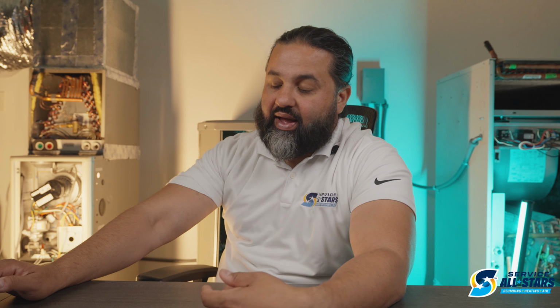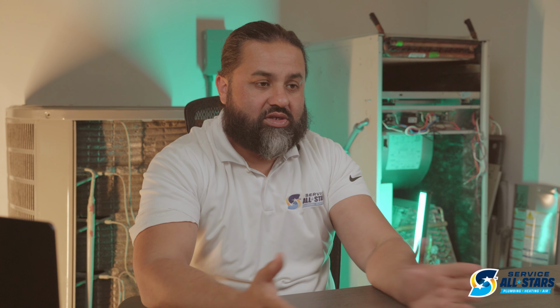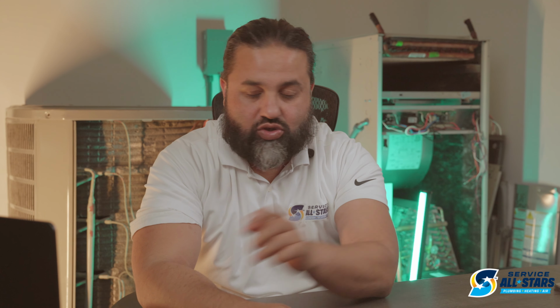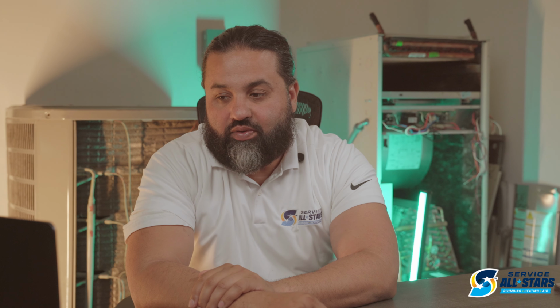So, like I said, our technicians, as they come out to your home, they're going to inform you if you have high static pressure, and we're going to get a second set of eyes out there to confirm the findings of the first technician to make sure that the static pressure is dialed in to where it needs to be, because it's a very urgent and serious issue. If we just leave it like that and not let our clients know, hey, this is what's going on with your system, we're actually doing a disservice to them, and anybody that does that. So I always tell clients, hey, look, if they're like, I'm going to get another estimate, okay, great, go ahead and go get this other estimate. But look, if they don't mention static pressure to you, don't trust them. And it's that simple. If they don't mention static pressure, don't trust them.